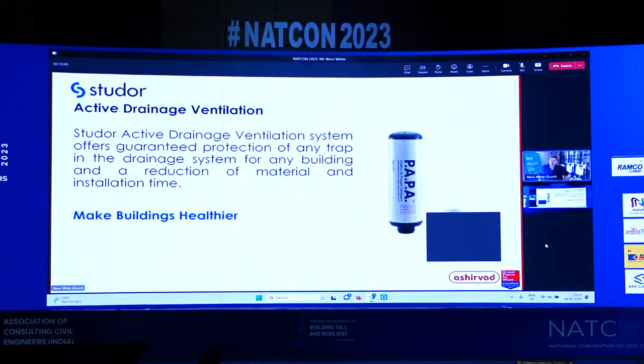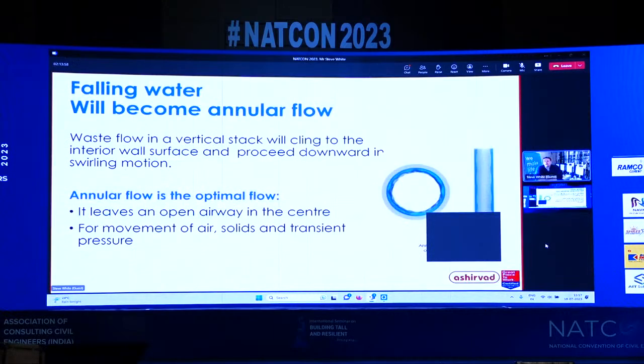So active drainage ventilation is basically an add-on product. In this case, it's a positive air pressure attenuator, and we also use AAVs that we put onto any drainage system to balance the pressures throughout the building. And we know that because we understand the fluids. So we know that in the fluid system, the water is annular, in the middle, where I said it's 80% air. We're managing the 80% of the air. We let gravity deal with the water flow within the pipe.